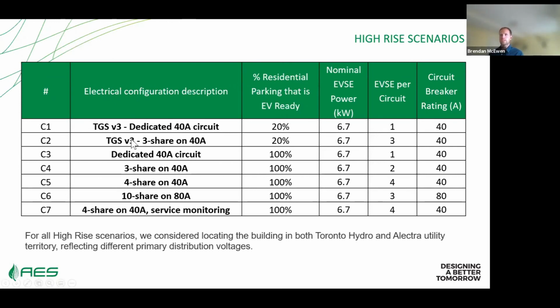In the third scenario, we have dedicated 40 amp circuits to each parking space, so no load management is going on - just a 208 volt, 40 amp circuit to every parking space for 100% of parking spaces. We also looked at a 3 share on 40 amp scenario for 100%, 4 share on 40 amp, and a 10 share on 80 amp.